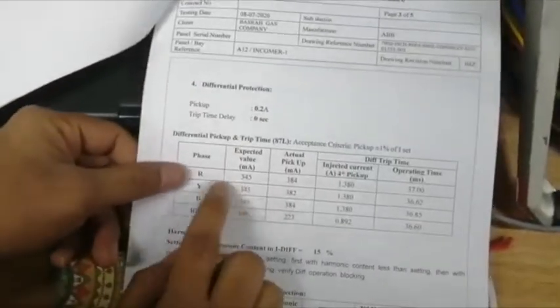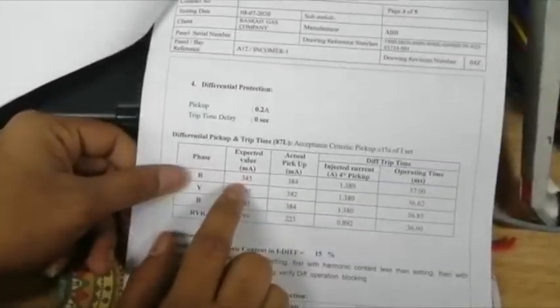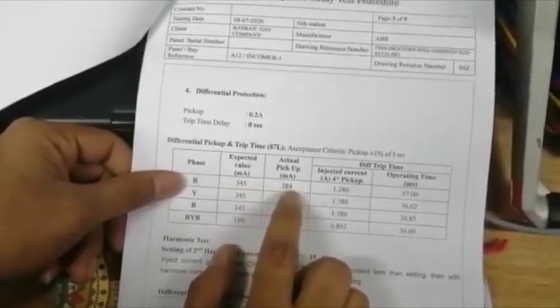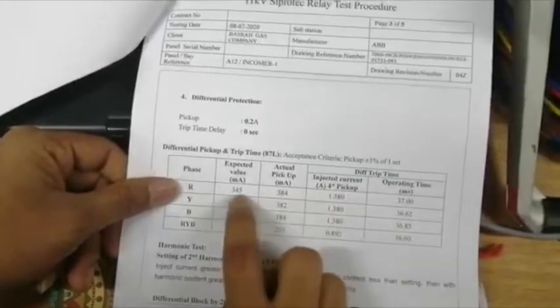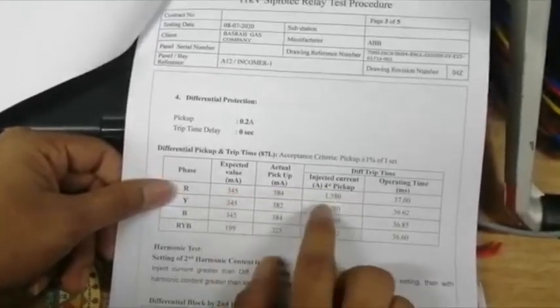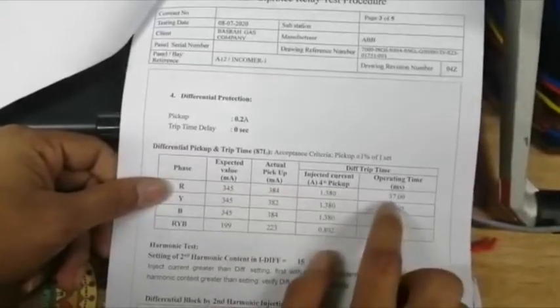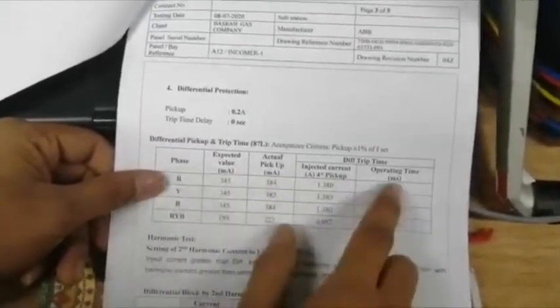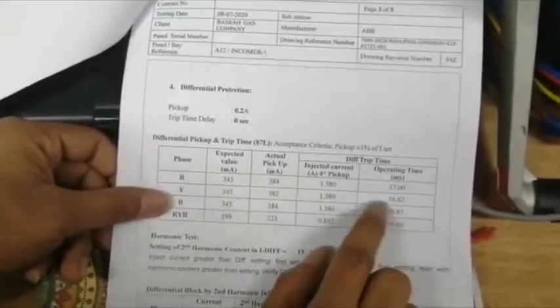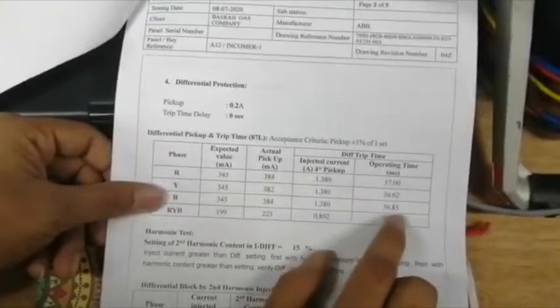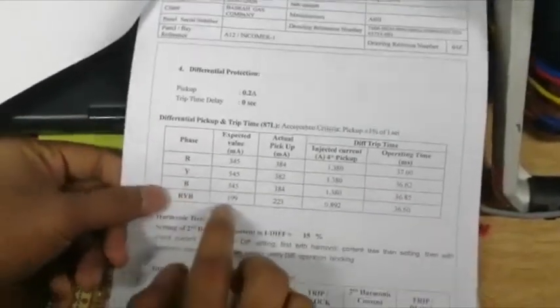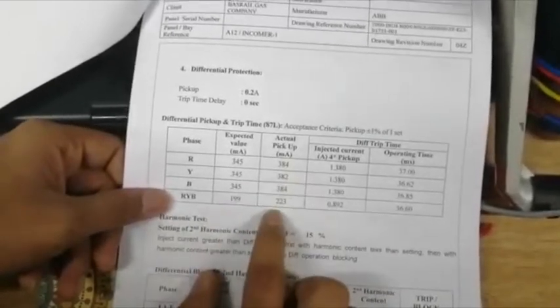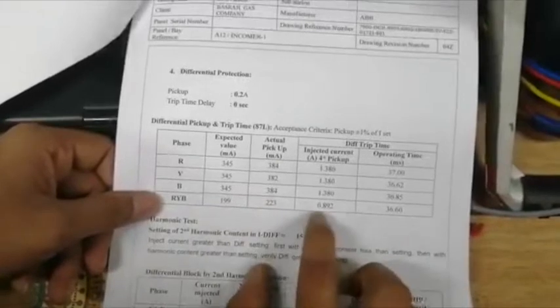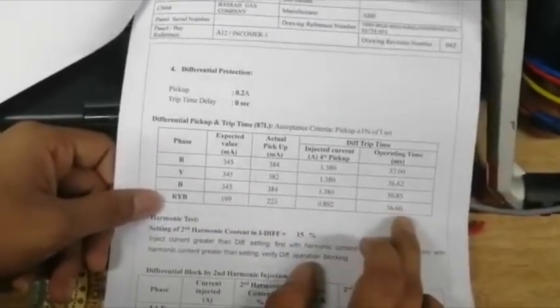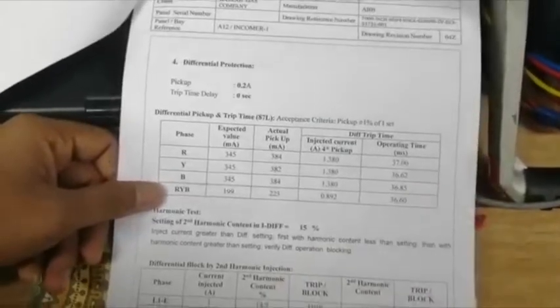And next, differential protection, our setting is 0.2. For 0.2, expected value for single phase 345. This is a calculated value. During testing, I got this 384 milliamps as a pickup value. 4 times of this pickup, calculated value 1.380. For this value, I got 37 milliseconds for R phase trip. Same Y phase, B phase, I got 36 point something as a trip value. And for 3 phase, calculated value is 199 milliamps, actual pickup value 223 milliamps. 4 times of this current, 0.892, I got 36.60 milliseconds as a trip time pass.